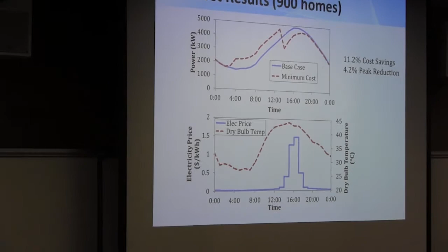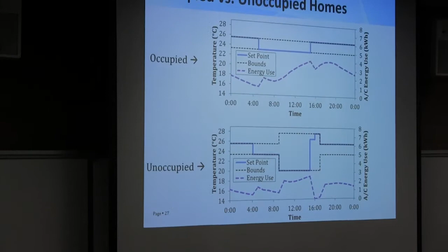Some interesting things come out of this. In that previous home you saw a 69% savings, but here the total savings is only 11%. If we look at why that's so different, we can see the difference between a home that's occupied versus not occupied. In the occupied home, the difference between the upper and lower bound set points is very small. You can't move the thermostat set point around much because somebody's there and they don't want you making the house really cold. So the bounds are small. When somebody's gone from the house, the bounds get quite large, and the difference is the amount of thermal energy that can be stored in the home.